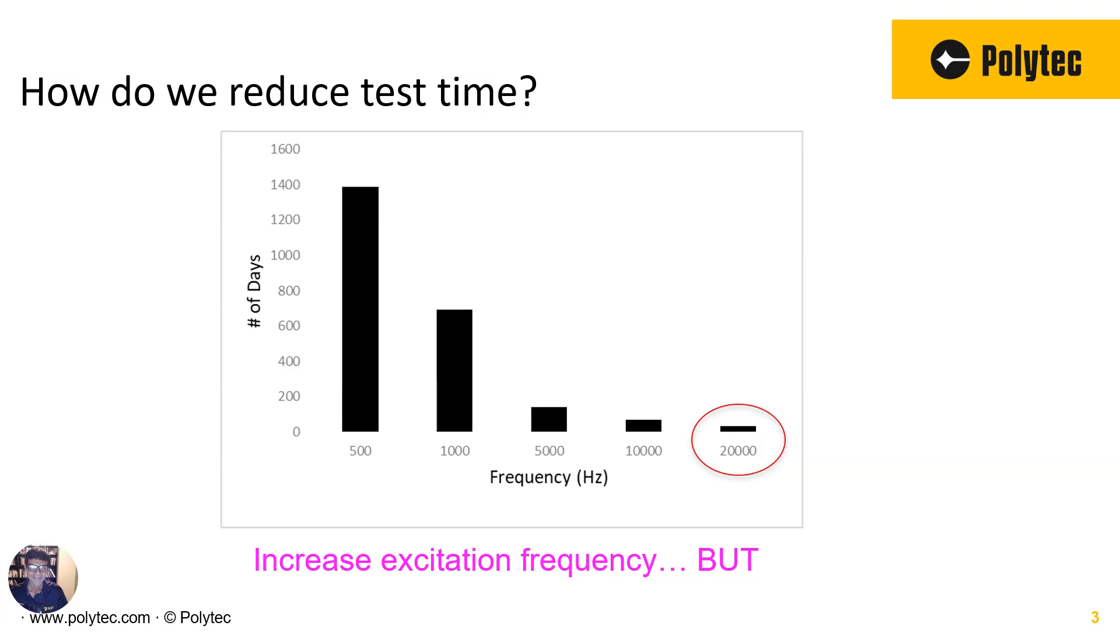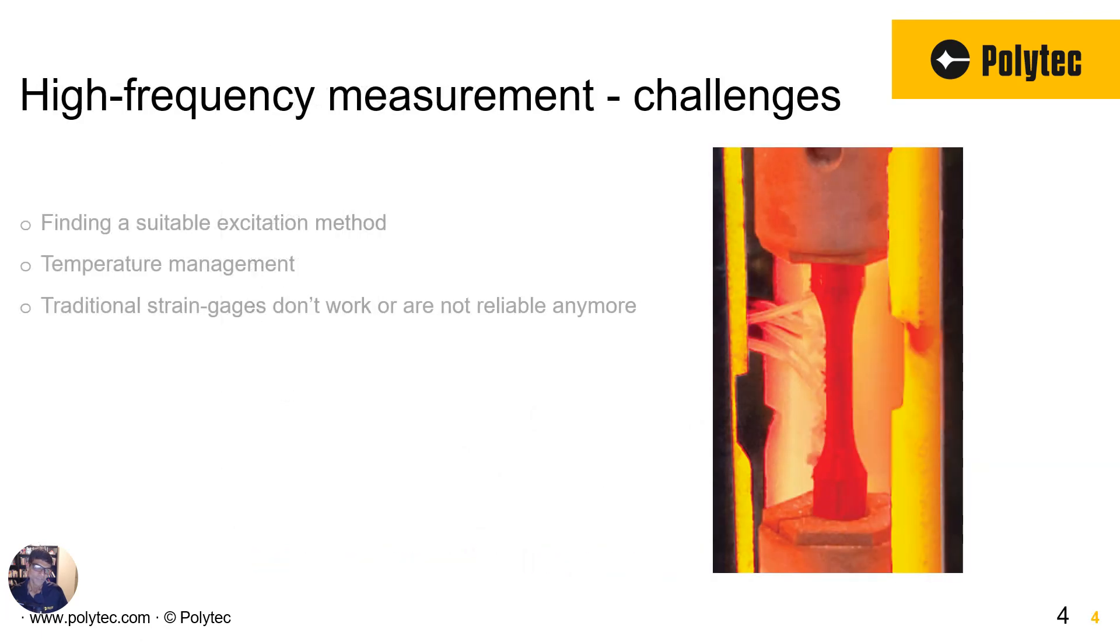However, a higher frequency comes with its own set of challenges. First of all, testing at 500 or 1,000 hertz is very different than testing at 20,000 hertz. It's not that straightforward to find a well-controlled, well-defined excitation methods specifically designed for this kind of fatigue test. Now, at higher frequencies, the temperatures are also much higher. So now you get into the temperature management side of things. How are you going to make sure that you're testing under similar conditions throughout your test? So that's also another challenge at high-frequency testing.